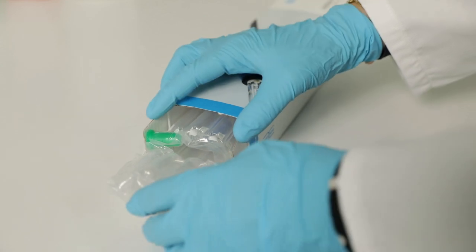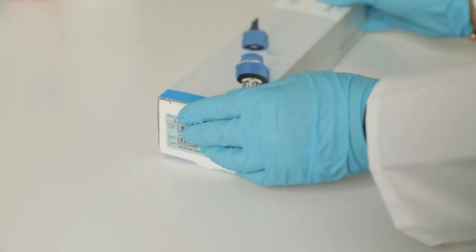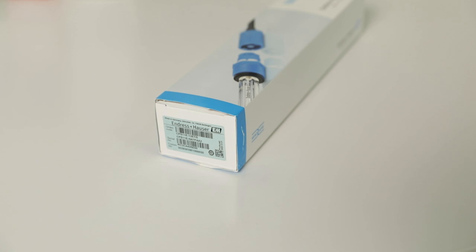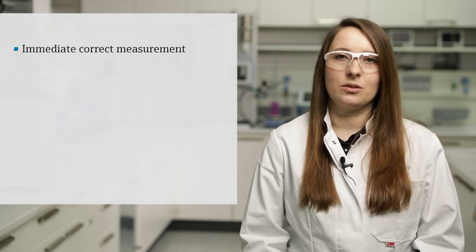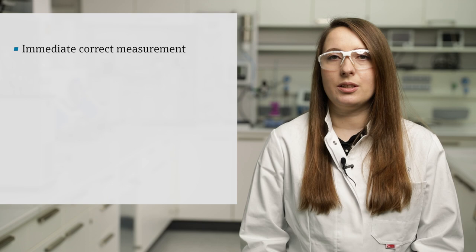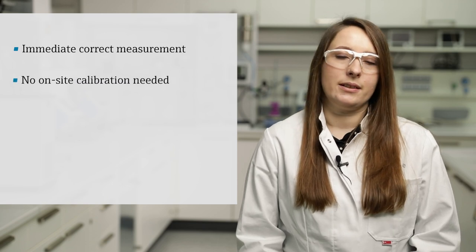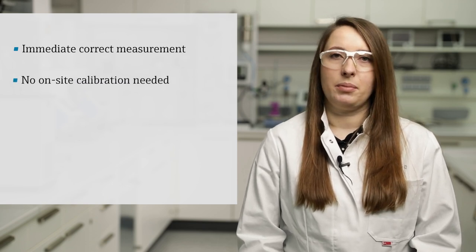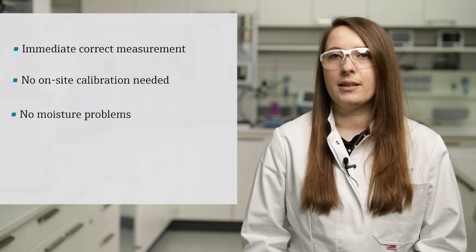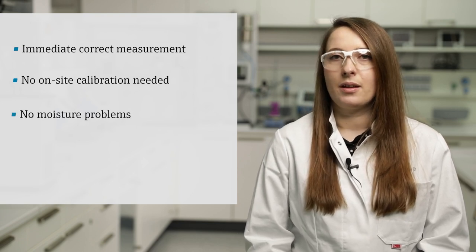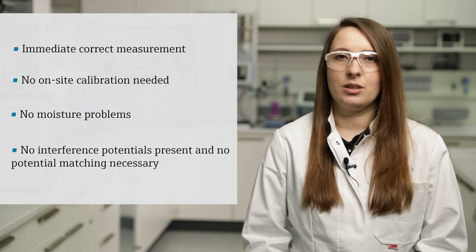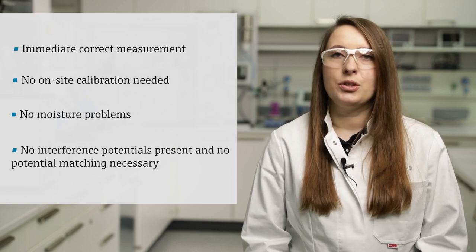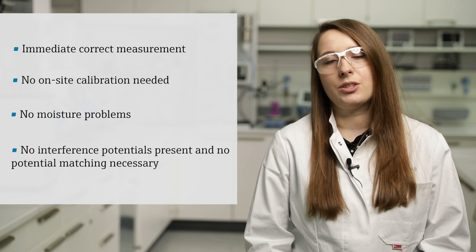Then place the sensor in its original packaging to protect the sensor during storage and transport. The advantages for you are immediate correct measurement as soon as the sensor is connected to a transmitter with Memosense technology. No on-site calibration, just plug and play. No moisture problems thanks to the Memosense plug. And no interference potential and potential matching due to the complete galvanic isolation of the sensor and the transmitter.